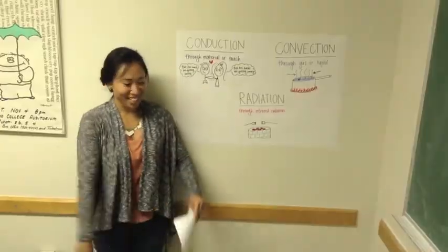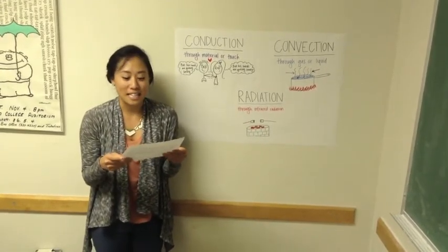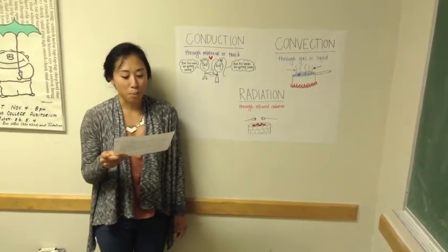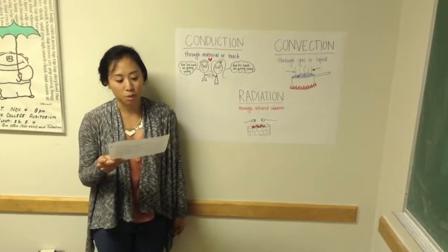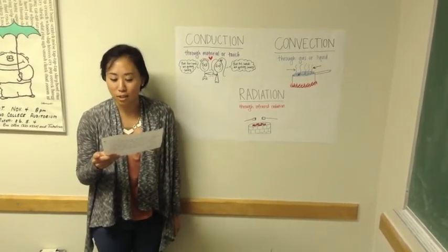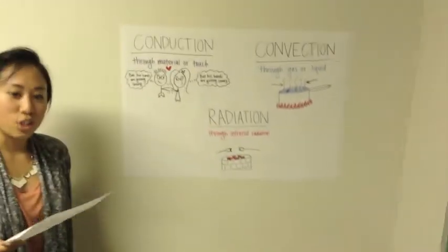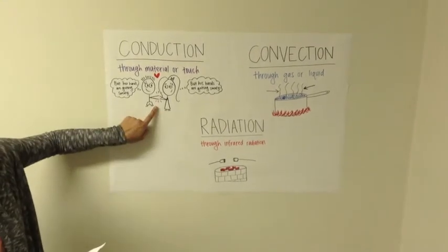Heat transfer is so important to us because excessive heat can result in shorter X-ray tube life. But proper utilization of heat transfer can help prolong the X-ray tube's life by dissipating heat effectively in daily use. Conduction, as shown here, is the transfer of heat through a material or by touching.